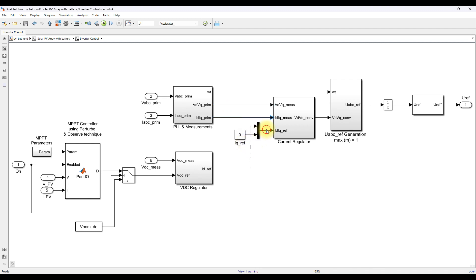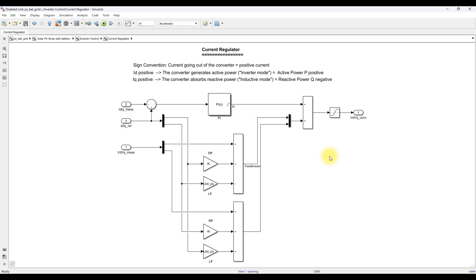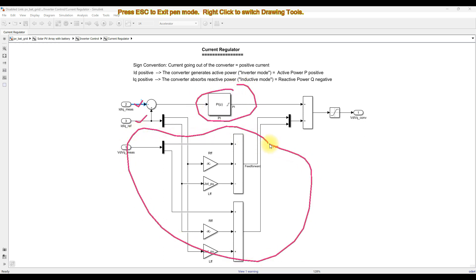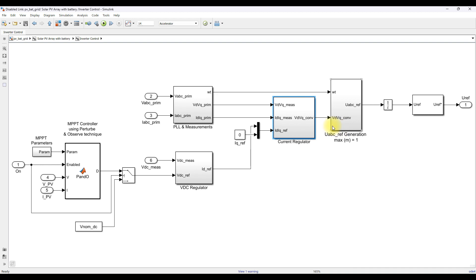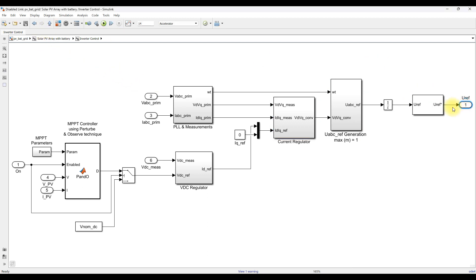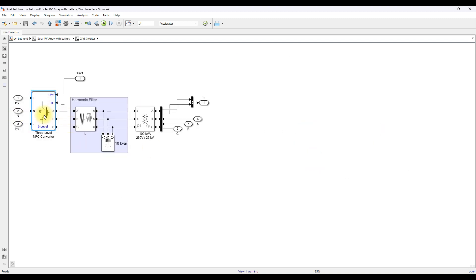With vd, vq, id, iq actual and id, iq reference available, we apply feed-forward decoupling control. The id and iq references are compared with actual values, processed via a PI controller, and feed-forward decoupling control logic is applied. The outputs are summed to produce final control signals vd and vq. These are then converted back to ABC form using inverse Park transformation, and processed via a modulator that generates control voltage references for the neutral point clamped converter to send real power to the point of common coupling.